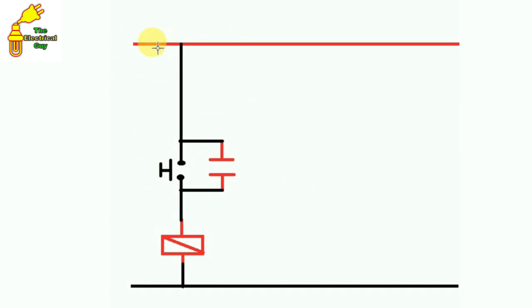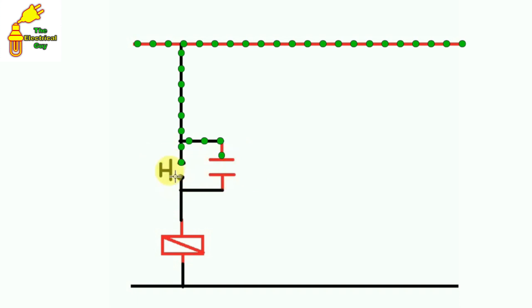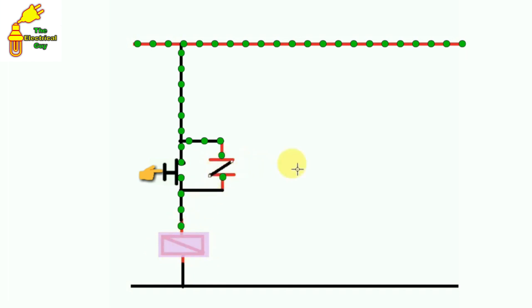In this condition, power supply will remain till here. It cannot flow further because this push button as well as the auxiliary contact — both are NO, meaning normally open. Both are open, so current cannot flow further. But when we press the start push button, current flows forward and turns on this contactor. The moment the contactor turns on, this auxiliary contact becomes NO to NC.